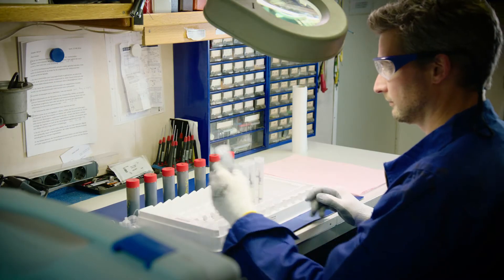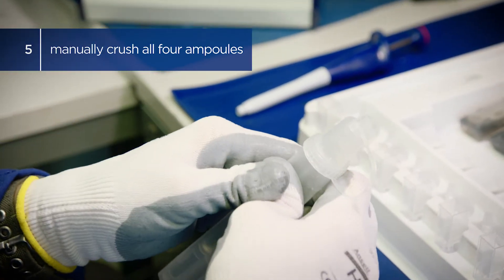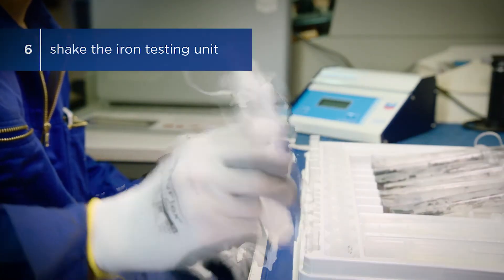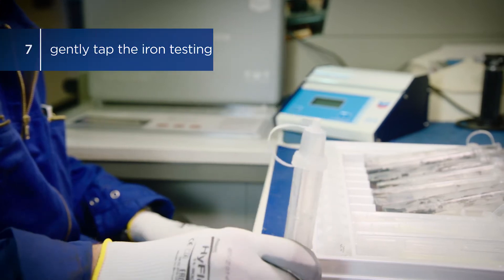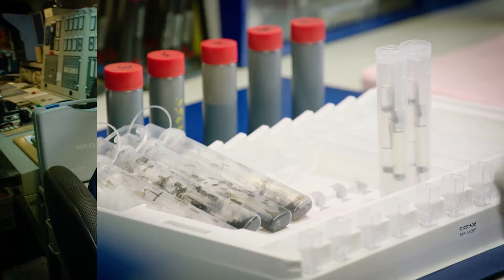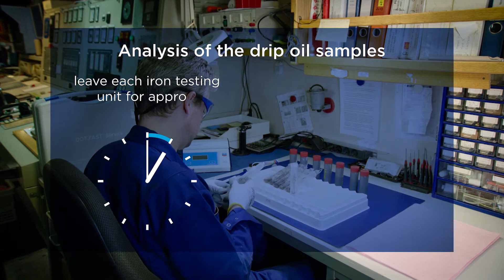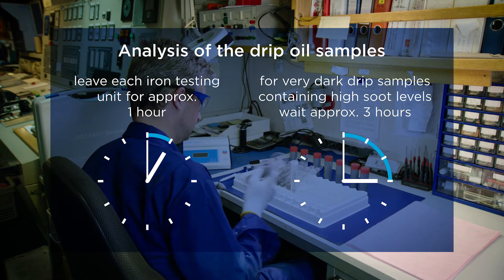Step 4: Firmly close each iron testing unit with a cap. Step 5: Manually crush all four ampoules in the iron testing unit into small pieces. Step 6: Shake the iron testing unit to assure all components are well mixed. Step 7: Gently tap the iron testing unit until content is collected at the bottom. Step 8: Place the iron testing unit in a sloping position on the DISPO rack. Repeat these steps for all ion testing units. Leave each iron testing unit for approximately one hour. For very dark drip samples containing high soot levels, wait approximately three hours.